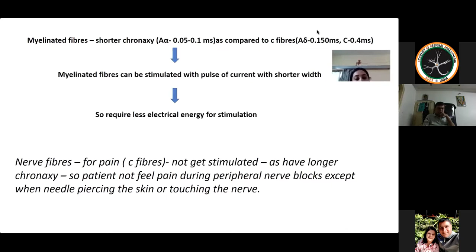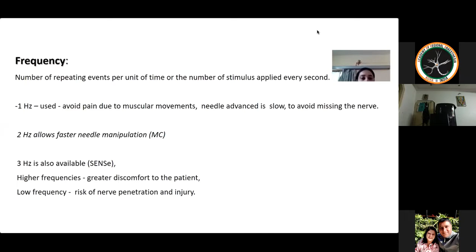So frequency is defined as the number of stimuli applied every second. The most common frequencies used are between 1 to 2 hertz, which is optimal for localization of a nerve. 3 hertz is also used. Now 1 hertz is used when we have to avoid any muscular pain or discomfort to the patient. The disadvantage of using 1 hertz frequency is that the needle should be advanced very slowly because there are high chances that we would miss the nerve. 2 hertz is most commonly used because needle advancement or needle manipulation will be easier as compared to 1 hertz. Now, if we use higher frequencies, there will be more discomfort to the patient, and with low frequencies you have the risk of nerve injury.